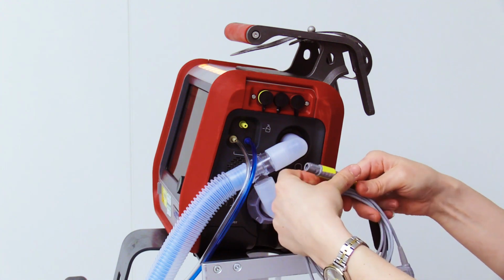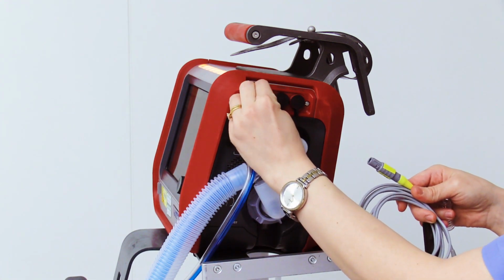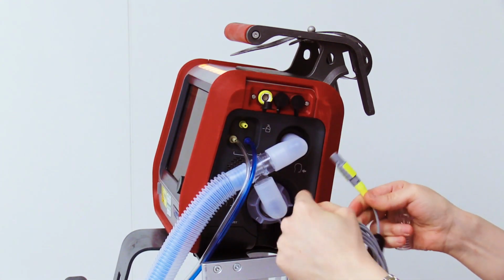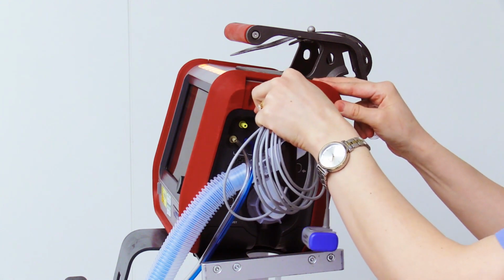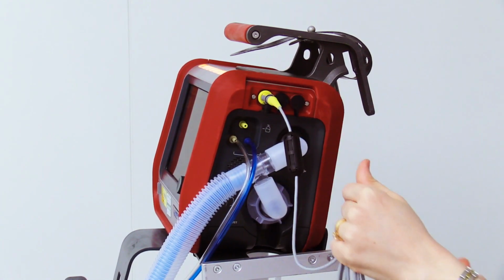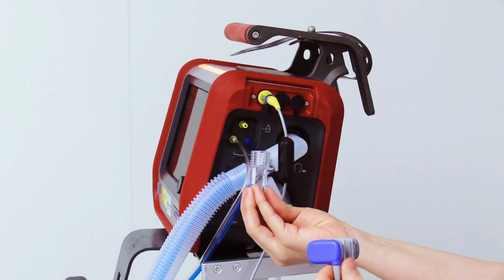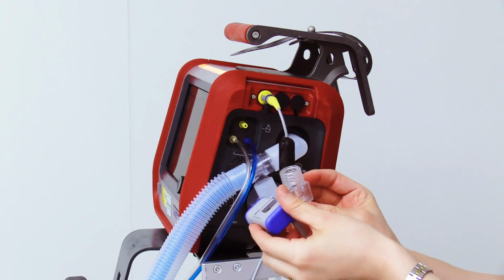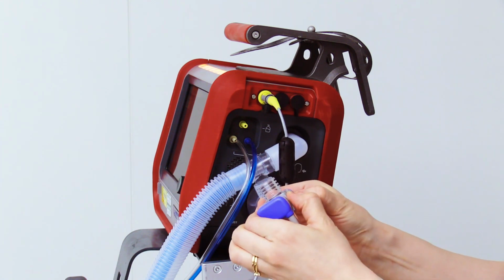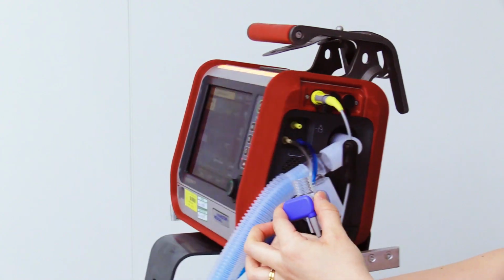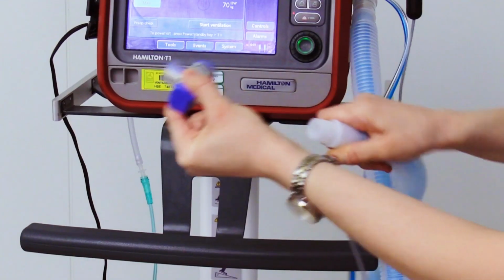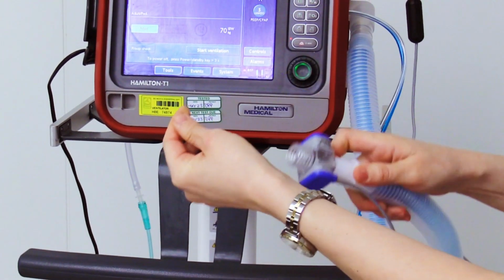If you want to monitor the end-tidal carbon dioxide, you need to connect a CO2 sensor to the corresponding connection port, which is this one. Slide the CO2 sensor onto the airway adapter, and press them together until you hear a click. Then connect the sensor with the airway adapter to the breathing circuit before the flow sensor.